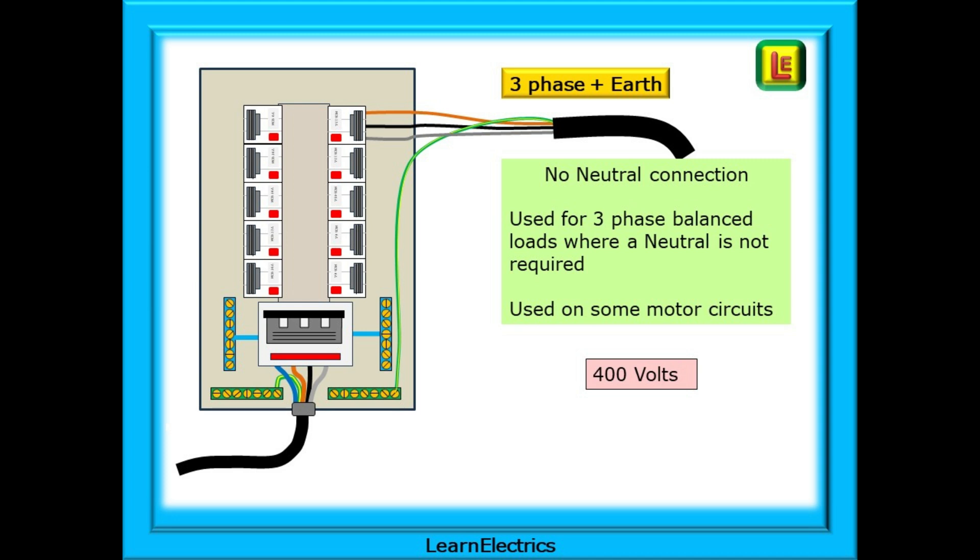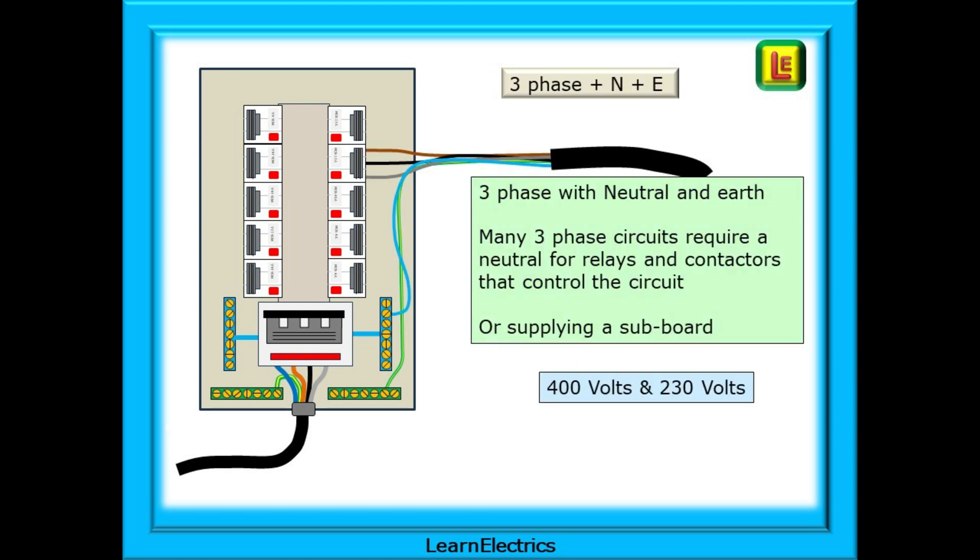Next is a three-phase plus neutral plus earth circuit, or five-wire circuit. This will give us a 400 volt supply and a 230 volt supply. Many three-phase circuits will require a neutral to create a 230 volt supply for relays and contactors that control the circuit, for instance. Or perhaps supplying a three-phase subboard in another part of the building. We will need to take all five wires to this subboard.